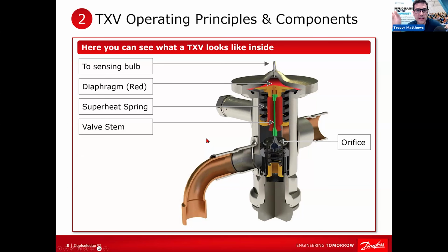Absolutely. Yeah, there's lots that don't, like on small, you still got cap tubes and things like that. But when you have a huge tonnage where there's a lot of load changing and stuff like that, you're going to see something that's balanced port. If you got fan cycling, you definitely need something like a balanced port, right? And so that's something that you'll see a lot of times. Yeah. The way I look at it and I think about it is that that bulb, like you said, is the opening force. If I squeeze, so right up here, and there's refrigerant and there's cross charges, and like you said, there's slow releases, fast releases. If it's pressure limiting valve, there's lots of different ones out there.